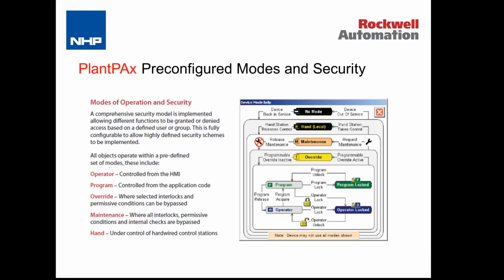The library is all pre-configured with modes and security. You can see there's a capture from one of the help files on the library, where it talks about the different modes that the objects have, and the state model, if you like, moving from one mode to the next. And also similarly with security, which I don't have an image there, but there's an A4 size table showing the security configuration for all of the objects, and the recommended user configuration to make use of that security in the system.